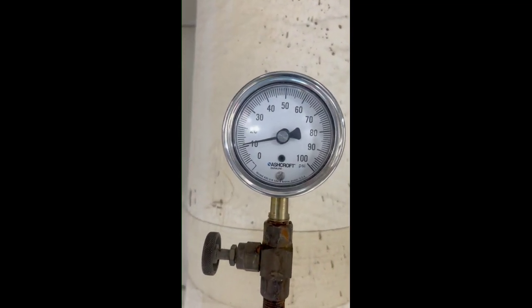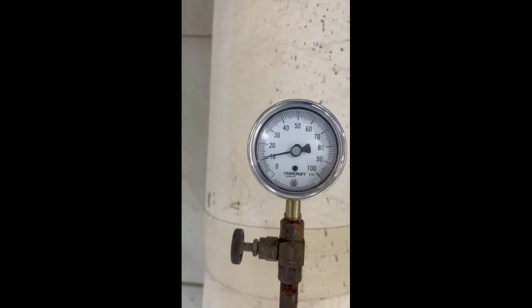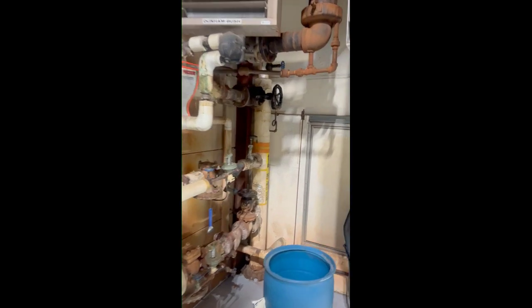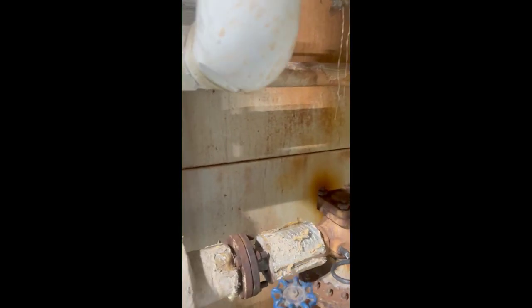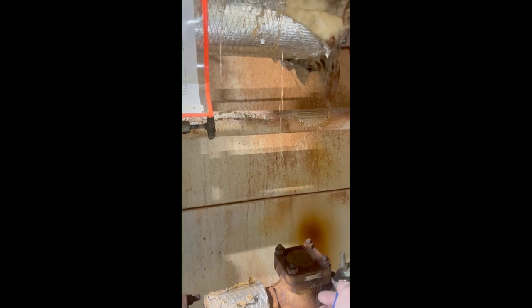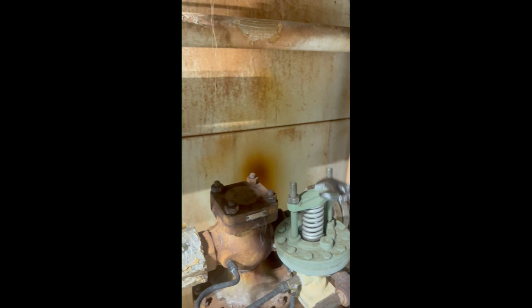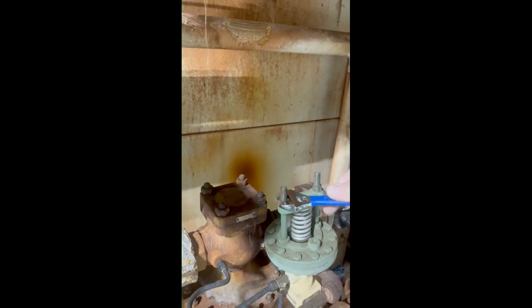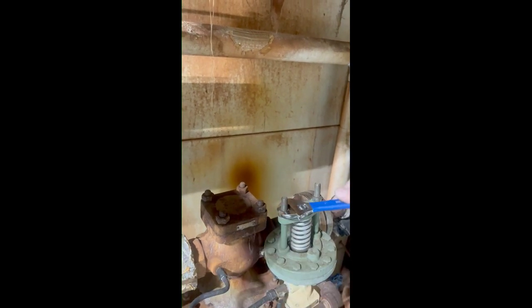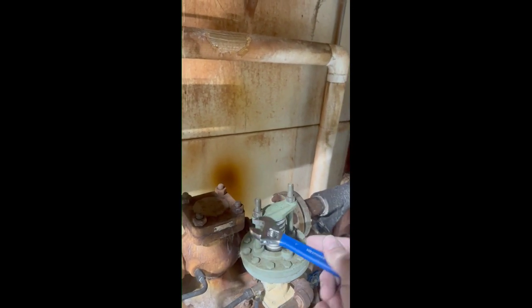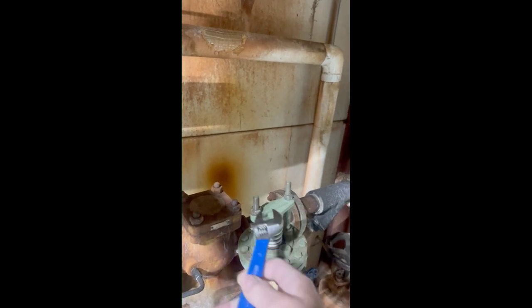And that pop-off valve is designed to pop at about 15 psi. So right now it's not, because it's under, but it was earlier when I walked in with this video, and that is some of the things that we heard. I said, hey, this is a high pitch leak that we were experiencing. So I have the basic PPE safety equipment on. Having insulated gloves would be a very big bonus, but right now I can tell you this should drive the pressure down. So righty-tighty, lefty-loosey.